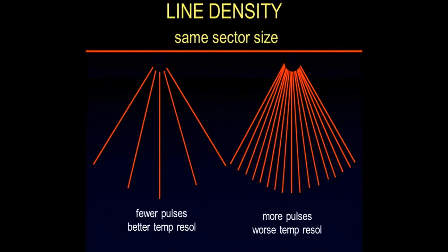You get higher frame rates when you image shallow with a single focus and a narrow sector and a low line density. You have a lower frame rate when you image deep with a multifocus and a wide sector and a high line density. Now for us, since most of the time we're looking at things that are dynamic, we need a reasonably high frame rate. If we're looking at an aorta, for example, we can live with lower frame rates and a little bit more data. What's the highest frame rate? M mode, right? Every pulse is an image. So M mode has the highest temporal resolution.